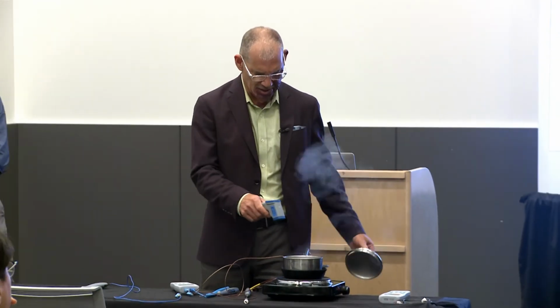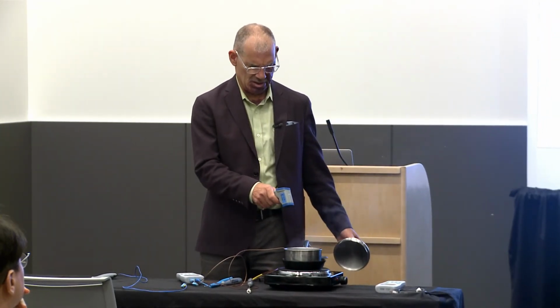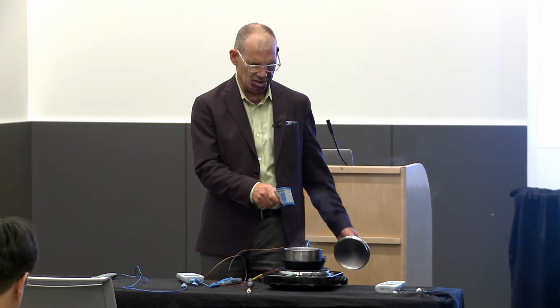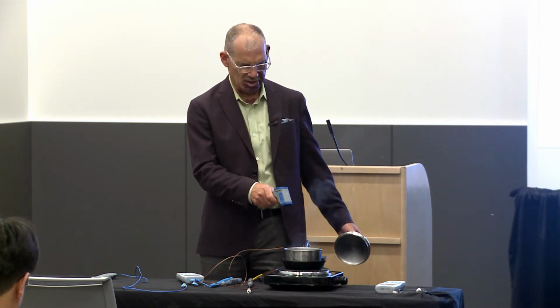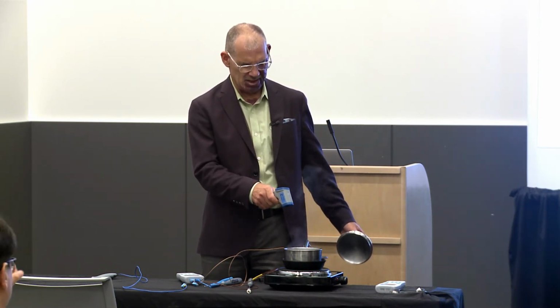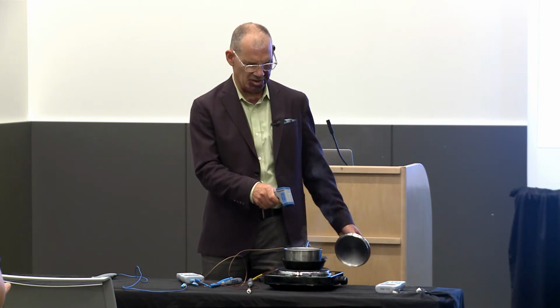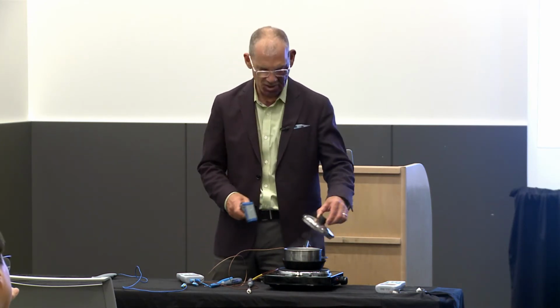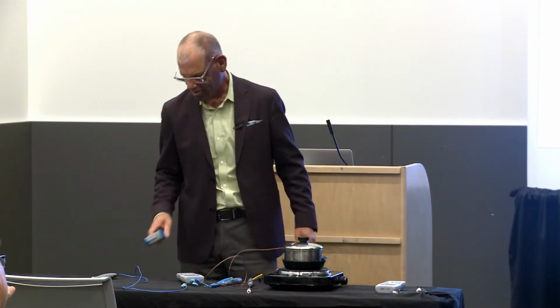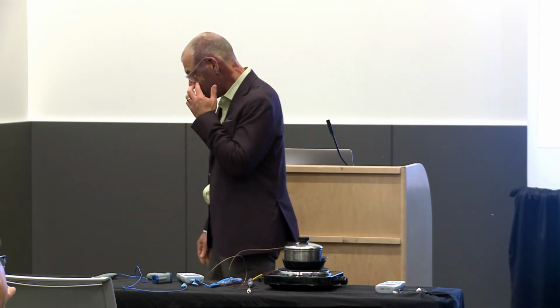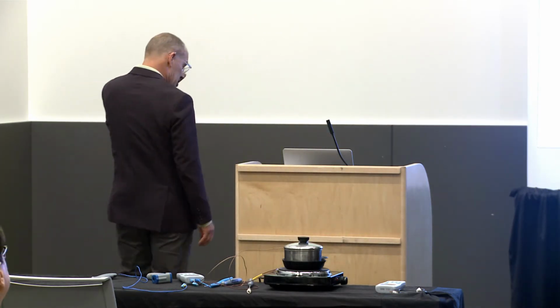Let's find out what the IR gun says the temperature is. That's pretty good, it says 95... 92, it's varying between 92 and 95 degrees. So it's not too bad at about 100, but as we saw, once you get up to 200 degrees it becomes very nonlinear very quickly. Anyway, that's what happens when you try to make a boiling point standard.